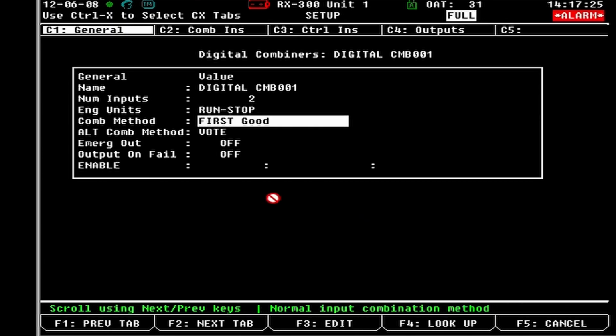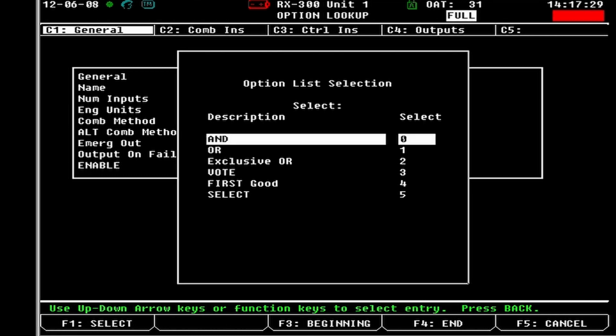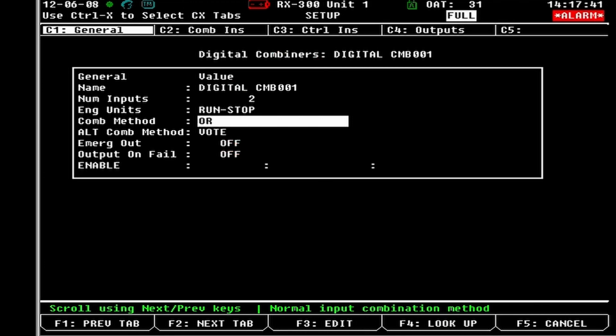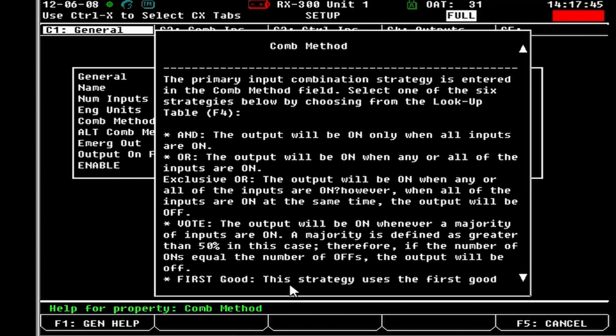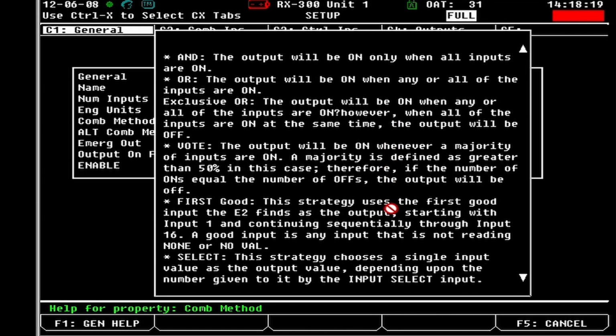Okay, so you have combination methods. If you look up, same thing. You have and, or, exclusively or, vote, first good, and select. So if you go to or, you hit the question mark. So we've gone over and or, vote. So this output will be on whenever a majority of inputs are on. A majority is defined as greater than 50%. And then exclusively or, the output will be on when any or all inputs are on. However, when all of the inputs are on at the same time, the output will be off. So not one you're going to use a whole lot, but I mean, you still could.